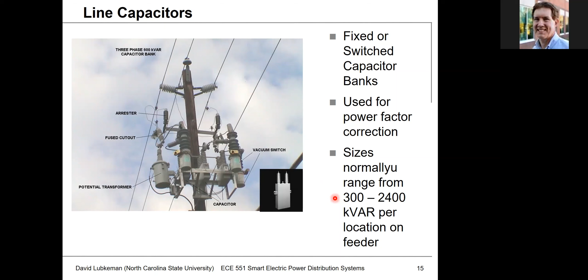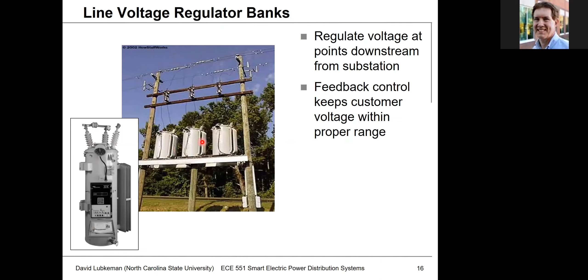For line regulators outside of the substation, we have these special units. These are what are called auto transformers, and we'll talk later on about what an auto transformer is. A lot of times if you have three-phase, these are rather heavy, so they'll come up with special mounts where these will be located in a platform in the field. And you'll see these outside as well. So there's a feedback controller on here. This is actually a controller on the unit. And what that controller does is it makes sure that the output voltage is regulated to a certain control set point.